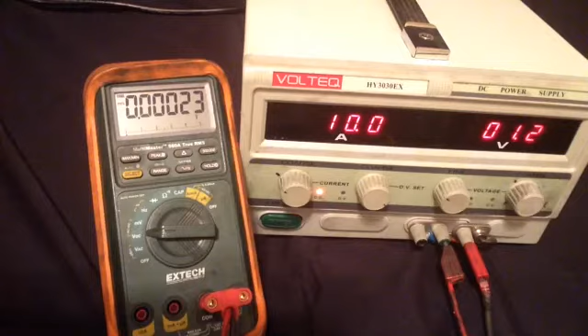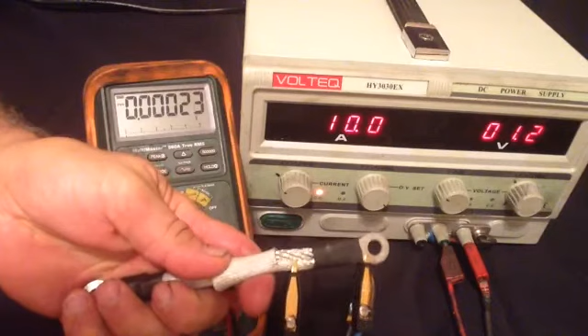Another thing that you can measure is the connections to a cable. Many times the crimps will be cold soldered, or they'll be overheated, and the crimp will have failed to make a proper electrical connection, even though it's still mechanically sound. This one here reads about 0.25 millivolts. That's a new one. And I've seen many that were a lot worse, but that still looked good. I recommend measuring how good a connector is before you assume it's good.